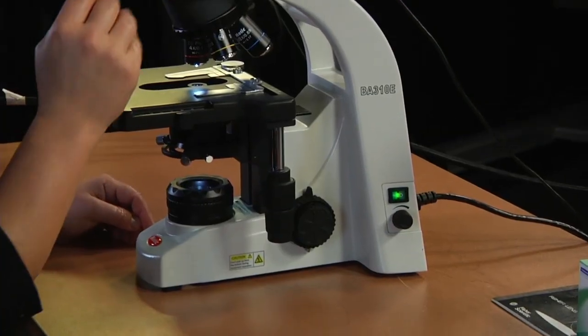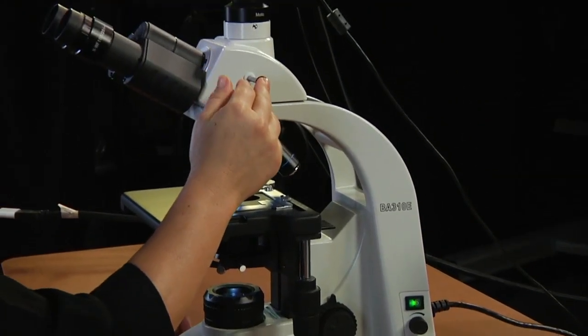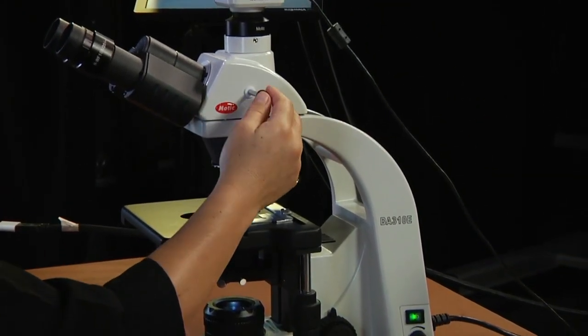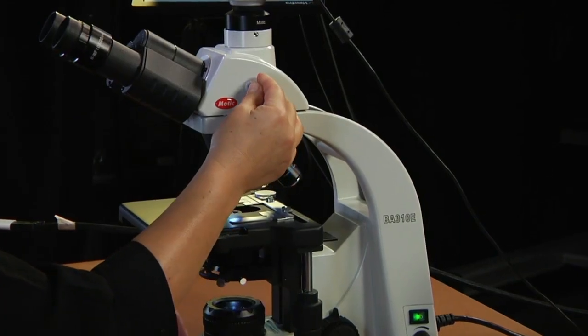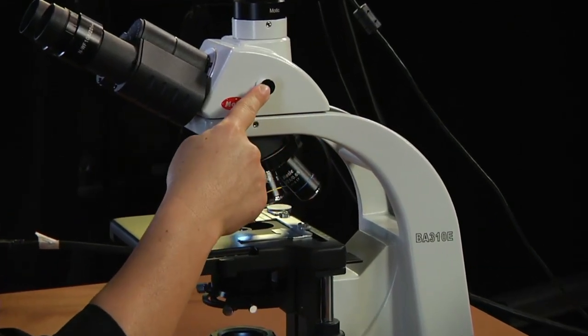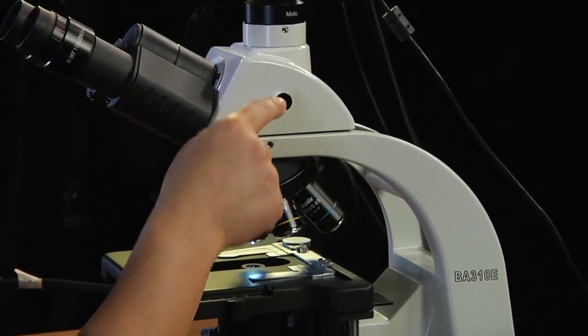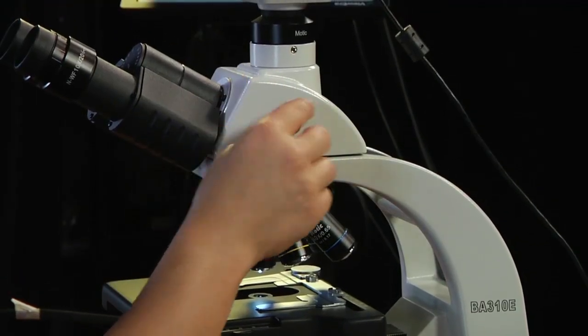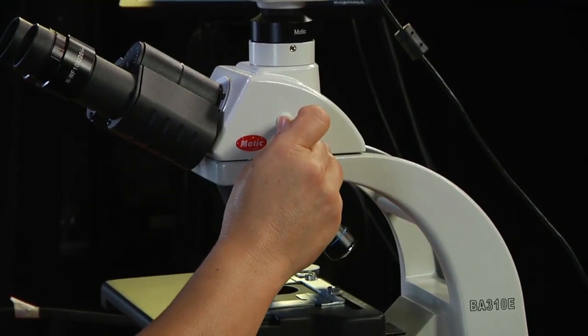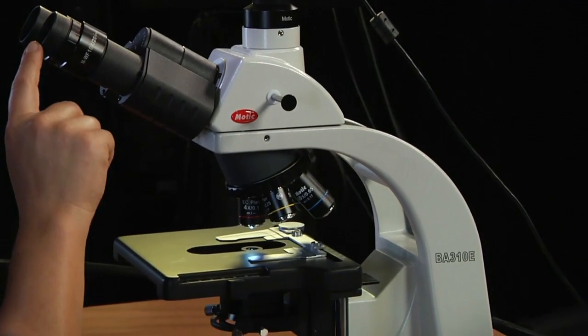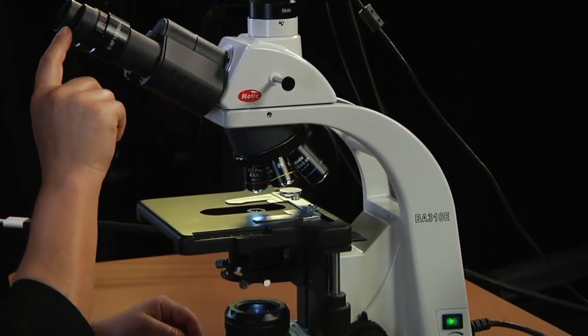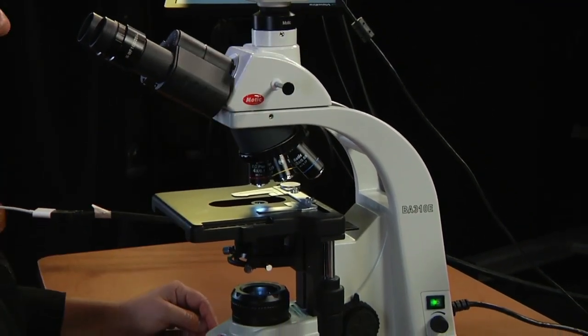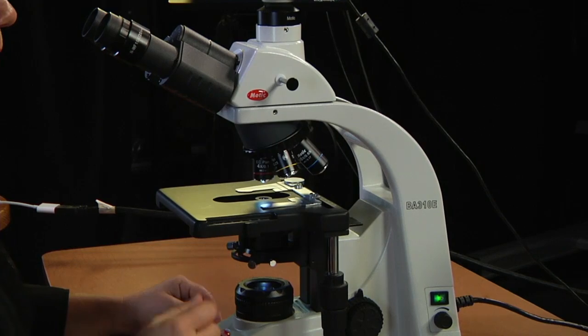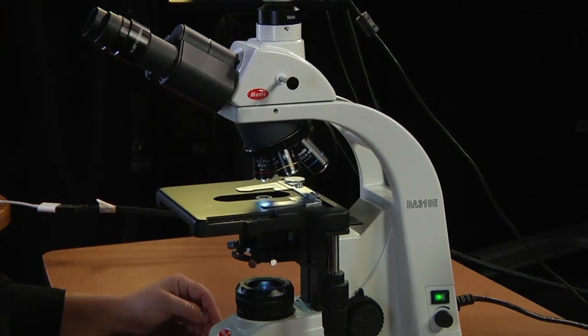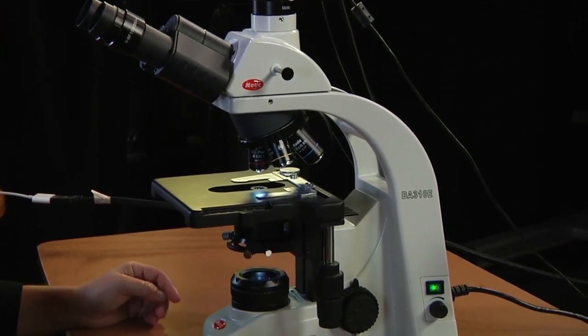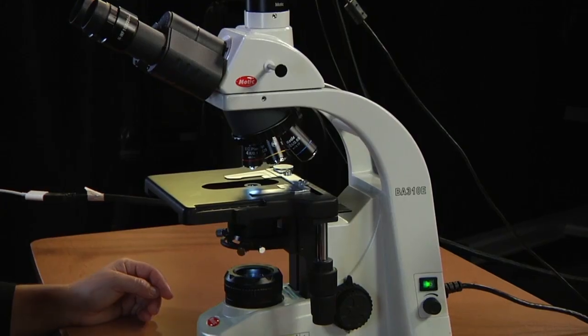On the top part of your microscope, you have one important switch, and that's to activate the camera. If the button is turned in, the camera will not see light. If the beam splitter is pulled out, you can see your image in the eyepiece and through the camera. So I would usually always just leave it pulled out. Alright, so we're almost ready to use the microscope.